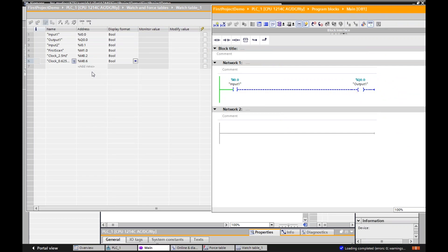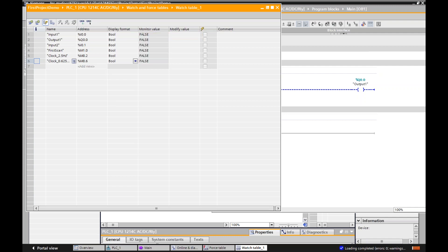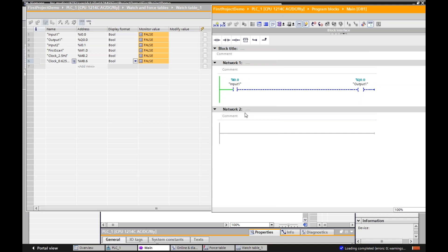I don't see anything changing, because remember — when I monitor something, I have to be live. So I can monitor all the values once right now, or I can monitor them continuously all the time. If I click on the sunglasses with the one, it's going to do one scan cycle and then say false. If I hit continuous, I should be able to monitor that here. And you can see the one input that I'm not using as I click on it.